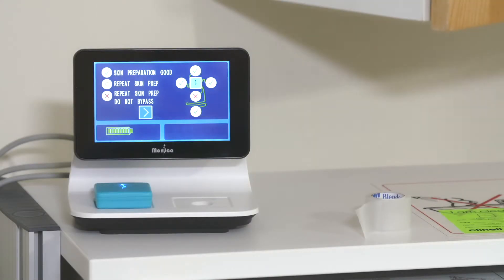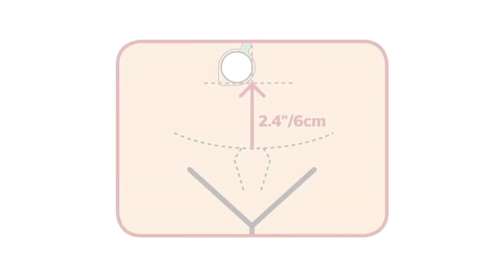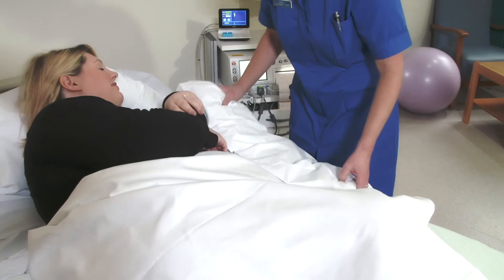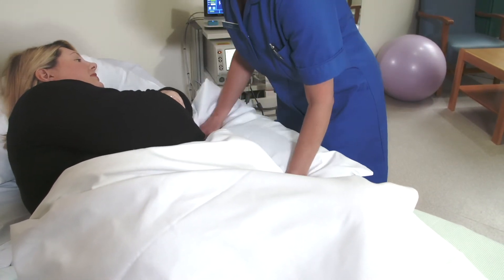Bypassing a red cross during setup or incorrect electrode placement, especially when the symphysis pubis is difficult to locate. In large moms, you may need to support the abdomen with a pillow or rolled blanket if they are lying on their side and the patch has been shifted away from the center of the uterus.